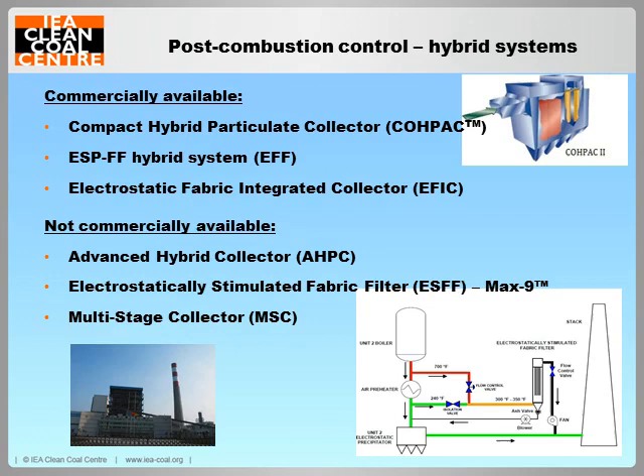The most common hybrid systems are the combination of electrostatic precipitation with fabric filtration to benefit from the advantages of both technologies. Several hybrid systems are listed here. ALSTOM, COHPAC, EFIC, and EFF are commercially available. The other three systems have all stopped at the demonstration stage due to funding. There are also other types of combinations of two or more PCDs, such as electrocyclone and electroscrubber, but there are no industrial applications yet.